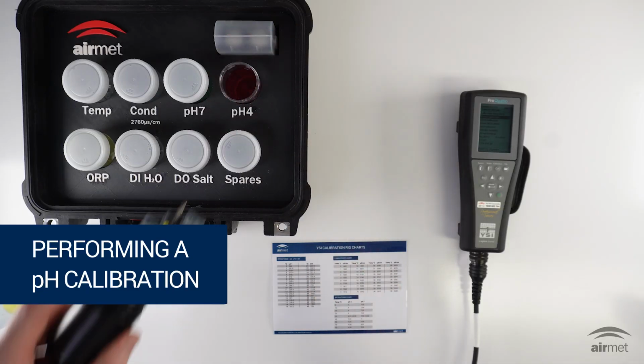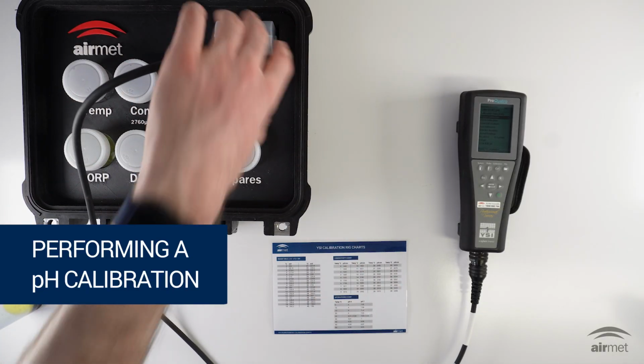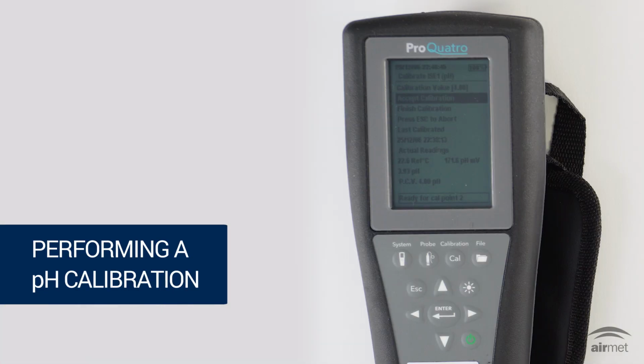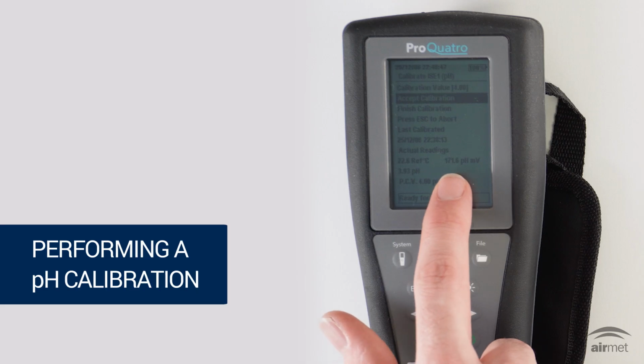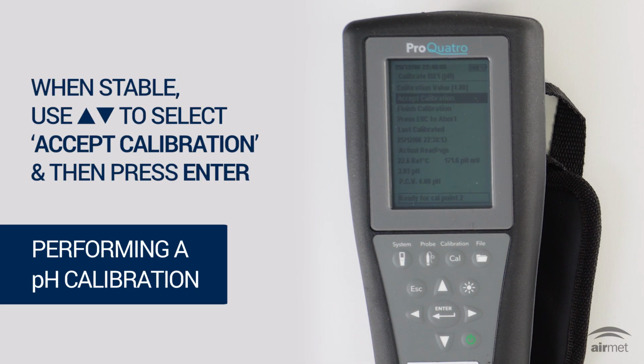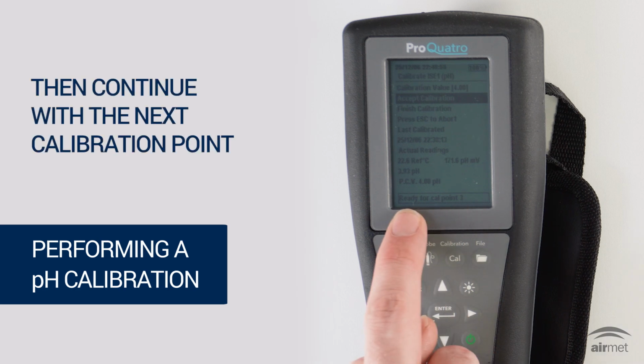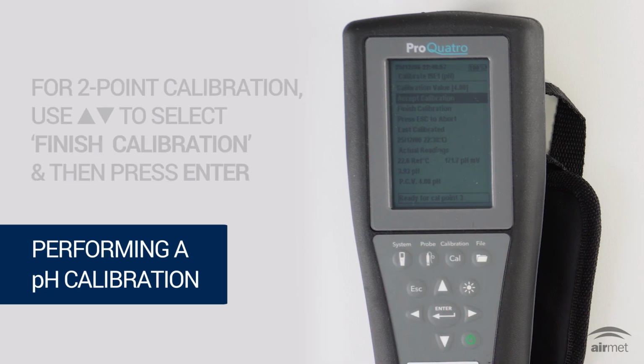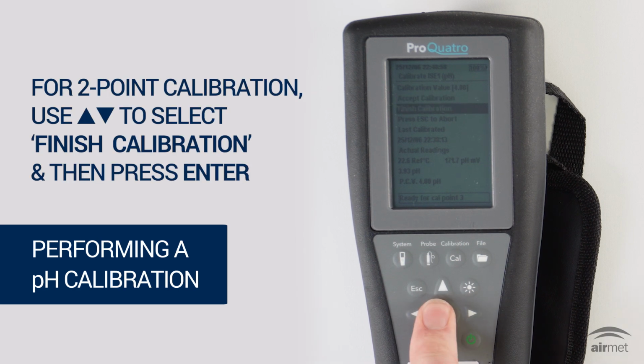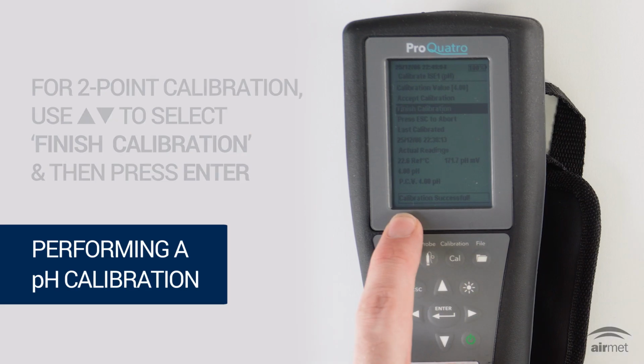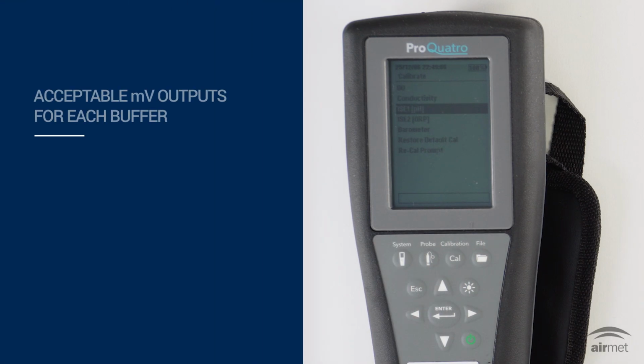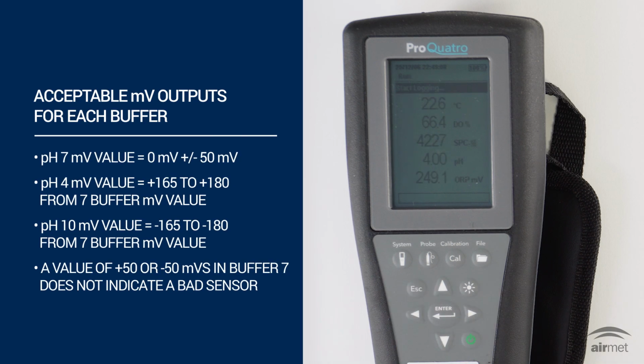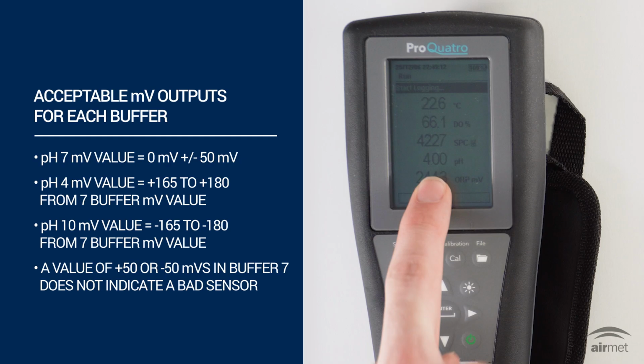Insert the probe into the next buffer solution, which is pH 4 in this case. Then wait for stability. Once the unit has stabilized, press Accept Calibration. The unit will then prompt for a 3rd-point calibration, or for a 2-point calibration, simply navigate to Finish Calibration and hit Enter. After stability is detected, the unit automatically adjusts the slope. If 2 points satisfy operational accuracy, finish here.